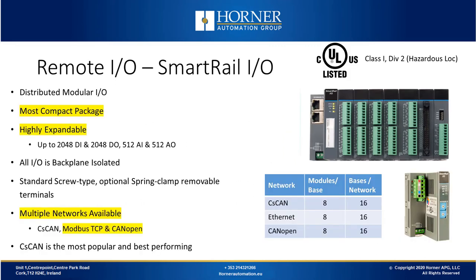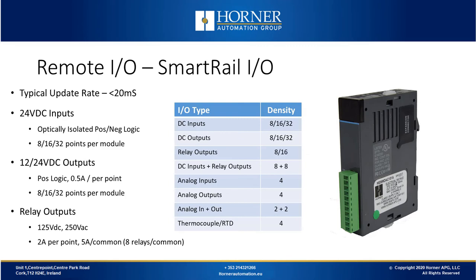Smart Rail IO is an elegant, nicely packaged, distributed modular IO. You can have up to 8 modules connected to each base, and up to 16 bases on each network. It's the most compact remote IO package and it's highly expandable. All the IO is backplane isolated. It comes with standard screw type terminal strips, and spring clamps are available and inexpensive. There are multiple networks available: CsCAN, Modbus TCP, and CANopen. CsCAN is the most popular and best performing, but CANopen is also very good. The typical update rate on the input side is below 20 milliseconds — as soon as an input changes, the Smart Rail immediately broadcasts that information and it gets to the OCS in a few milliseconds.